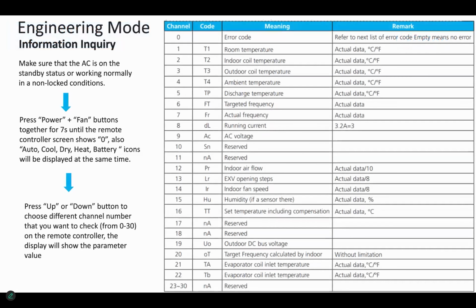Let's go back. I don't want to go that far in. 17 and 18 are reserved. 19 is your outdoor bus DC voltage. 20 is the target frequency calculated by the indoor. 21 and 22 are TA and Tb.